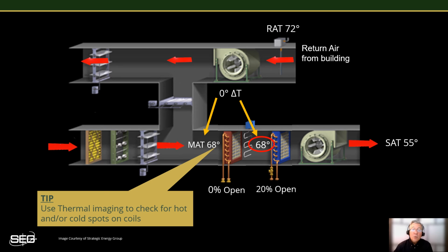I've seen sites where they've had plans to add an additional 1,000 tons of cooling capacity because their chiller plant could no longer keep up with the campus's cooling load, when in fact, they had plenty of capacity to meet the true cooling load. They simply had numerous heating valves that were leaking by, which were artificially eating up much of their cooling capacity, and as a result, significantly driving up energy consumption and cost at the same time.